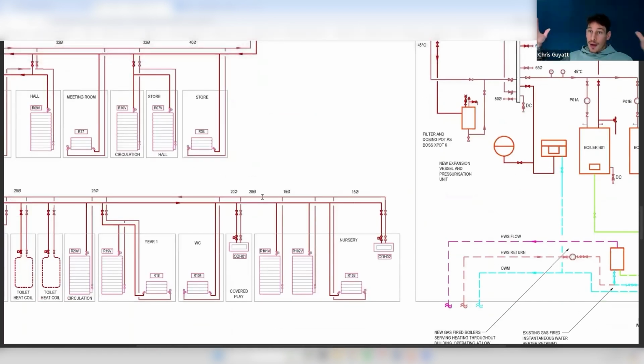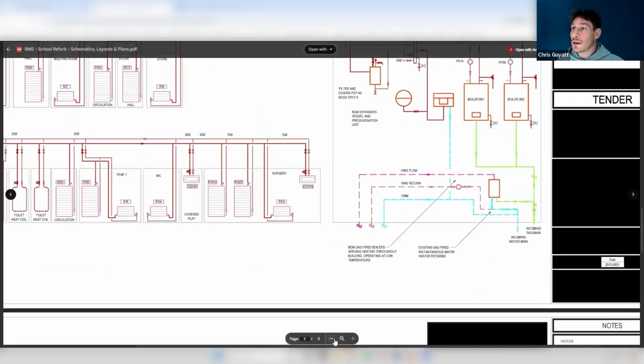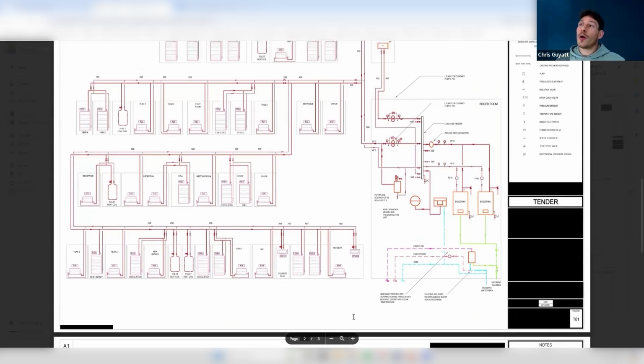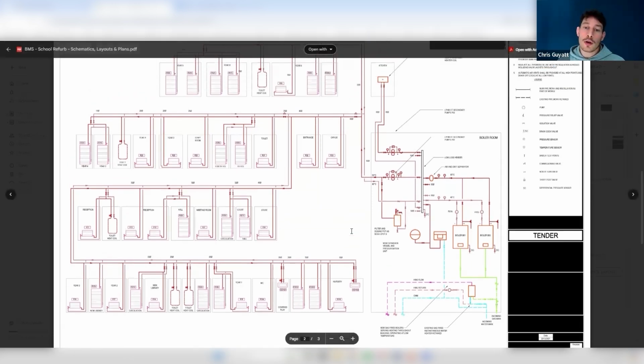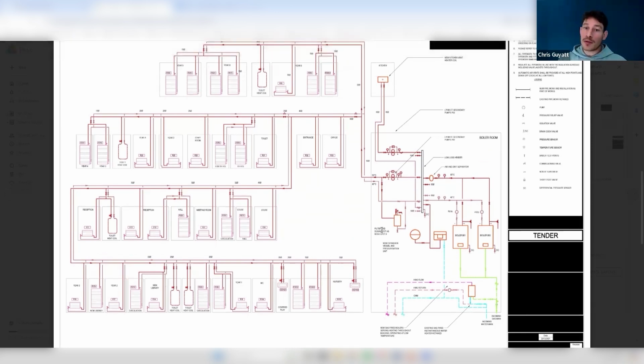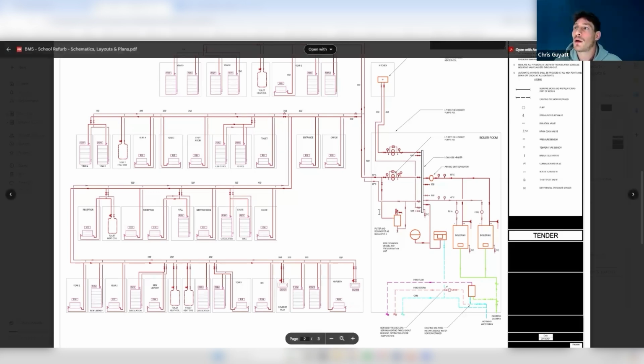So that's a big picture view of the project. I'm not going to go into more detail than that, but the M&E designer - the mechanical electrical designer/specifier - then writes a spec detailing what they want you as a controls engineer to do with this system: timings, how boilers should fire up, what should happen if something fails, etc. It's pretty standard - if you get a spec from one M&E designer for a BMS system and then another spec from a different designer on another project, they're all pretty much the same. Once you get into BMS controls, it's pretty standardized how you do things. Obviously there might be more pumps or valves, slightly different equipment, but the principles are pretty similar.